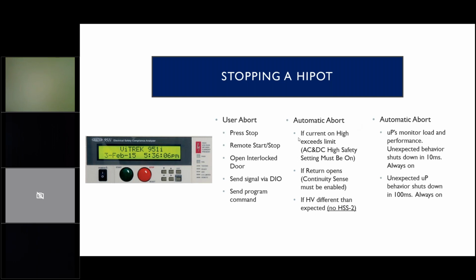If the current exceeds the limit, and that's assuming you've got the high safety setting turned on, which is the default, then if that high current gets too high, it's going to automatically shut down. Now, it's important to have a return on these systems, and there's a continuity sense which must be enabled, and is by default. If someone pulls the black wire, not the hot wire, but the black wire, that return opens, and it will shut the system down automatically. Same if the high voltage is different than expected. So let's say you're putting out 30 milliamps of current, and only 10 milliamps is coming back. Well, it's kind of like a GFI. It realizes there's something wrong, and the system shuts down automatically.